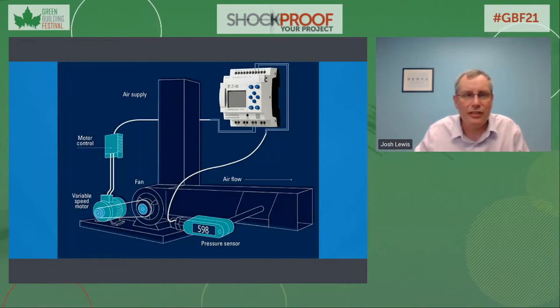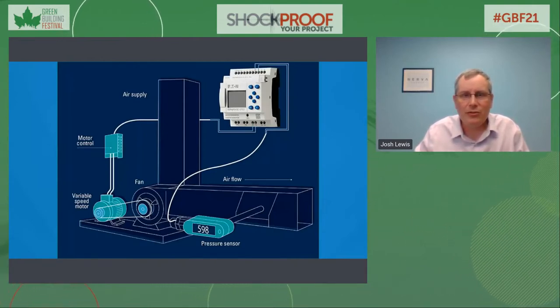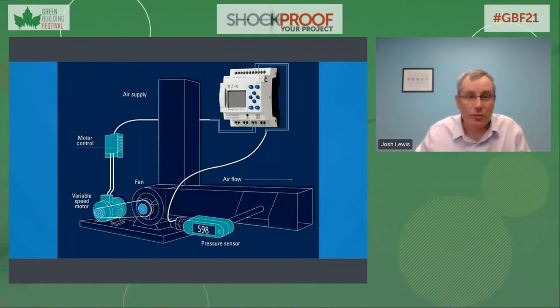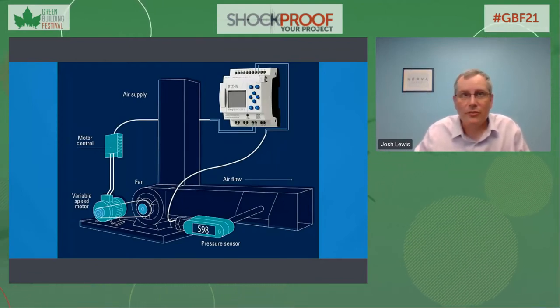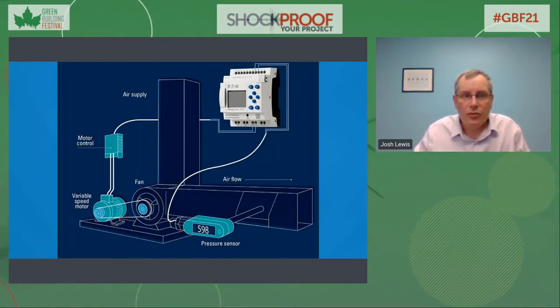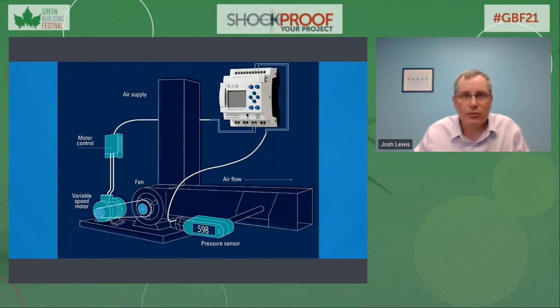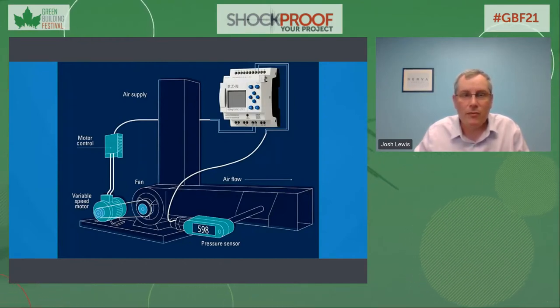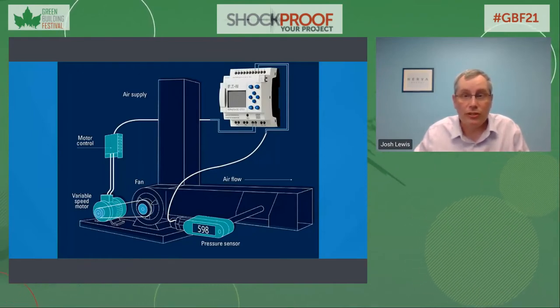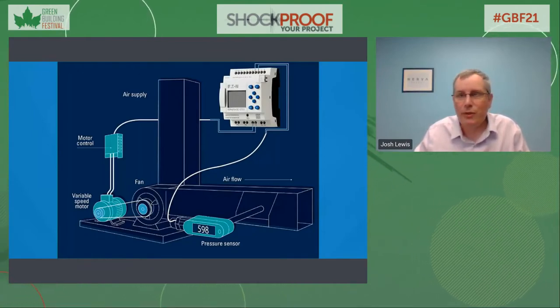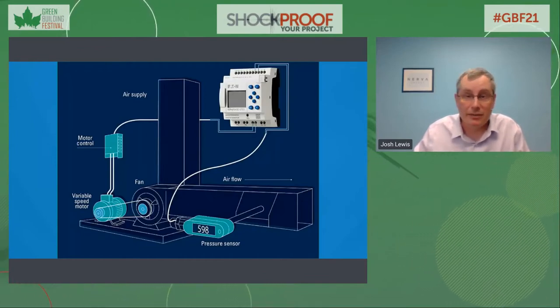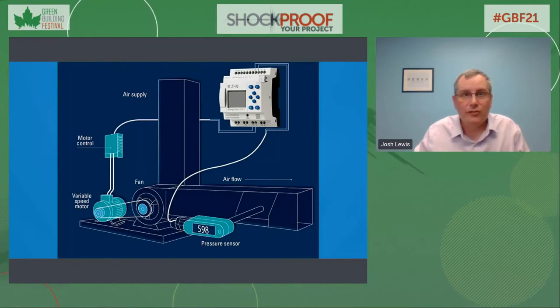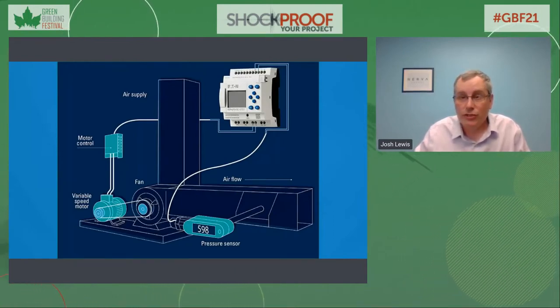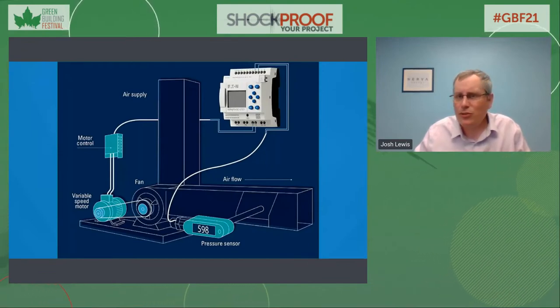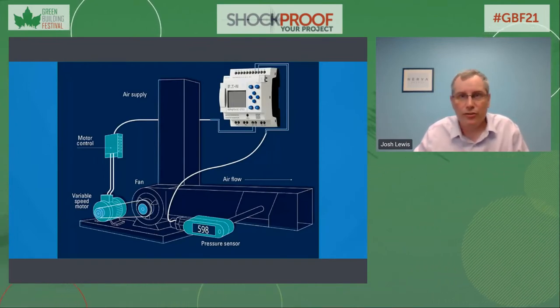To improve the energy efficiency of HVAC systems, they've often been designed or upgraded to include variable speed drives, also known as variable frequency drives. These electronic systems allow for the fan speed to be dynamically changed through either manual or automatic intervention. In most cases, the drives have been set up on a schedule and configured with a limited maximum fan speed in order to reduce energy consumption and carbon emissions. Unfortunately, during a pandemic, this strategy must be altered. Instead, we want to maximize fan speed, which maximizes air circulation of the existing system. When making this change, the original settings should be recorded and saved so that the parameters can be reset to their existing values once the situation which demands that we prioritize indoor air quality over energy efficiency has passed.